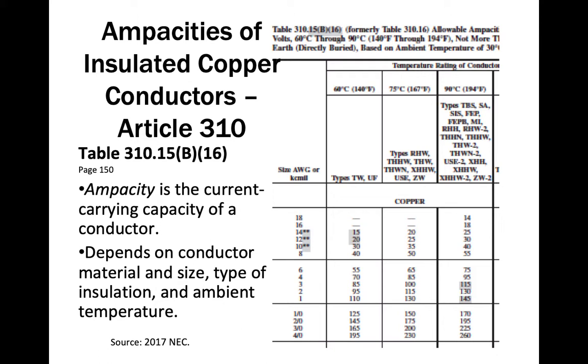Right, a couple words on this. When we go through our derating of ampacity, these ampacity ratings are for 86 degrees Fahrenheit and 3 current carrying conductors in a pipe. If I get more conductors in a pipe, I have to derate or downsize the ampacity of that conductor. If that conductor goes through a warmer condition than 86 degrees Fahrenheit ambient temperature, then I have to decrease the ampacity or the carrying capacity of this conductor based upon those conditions.